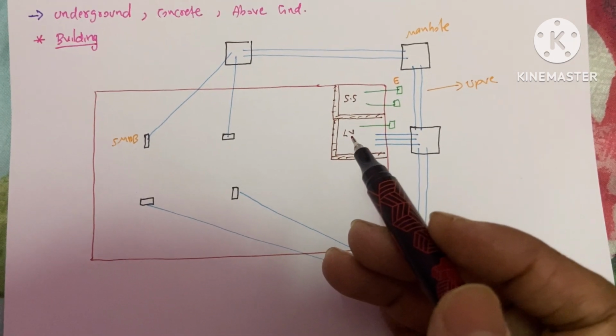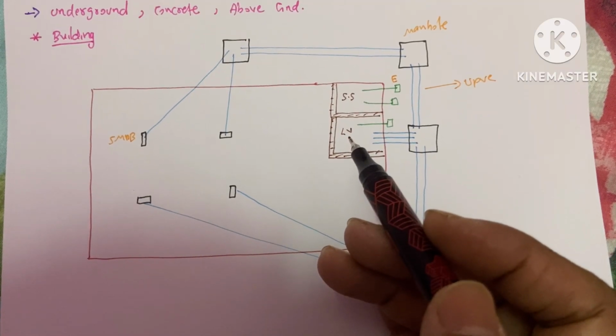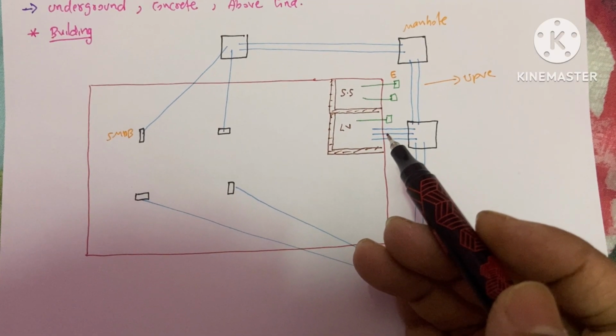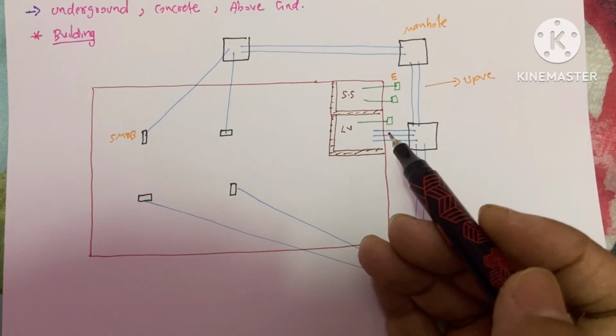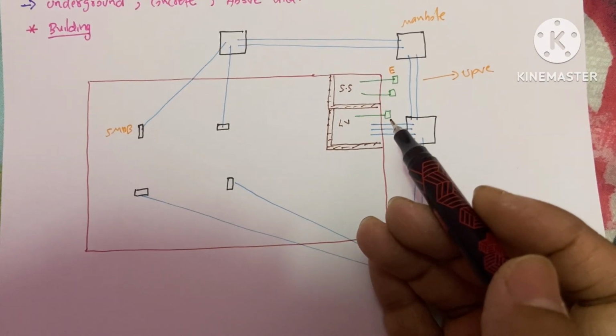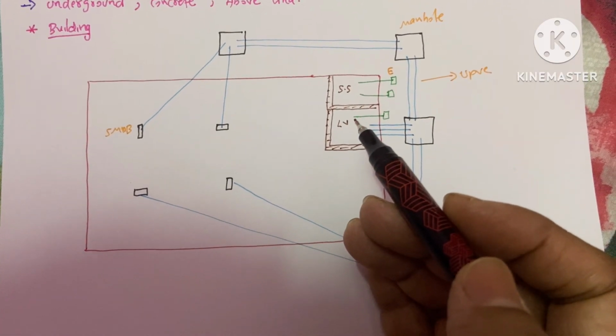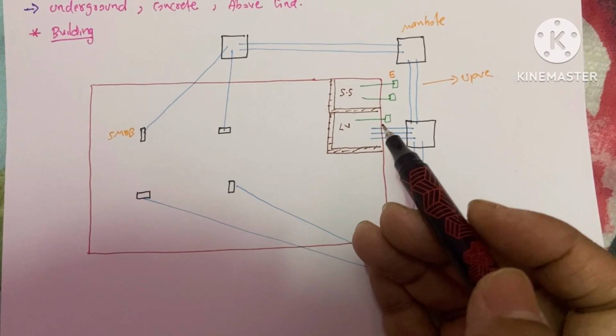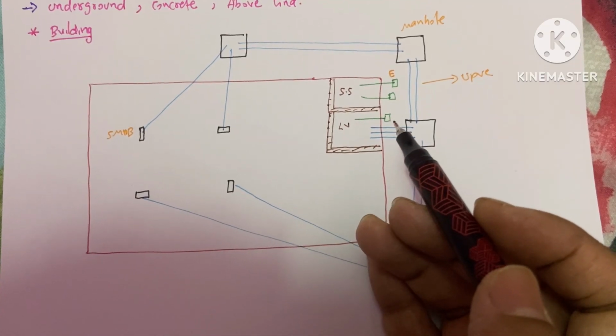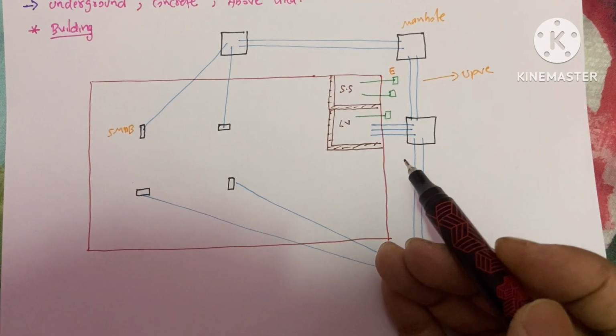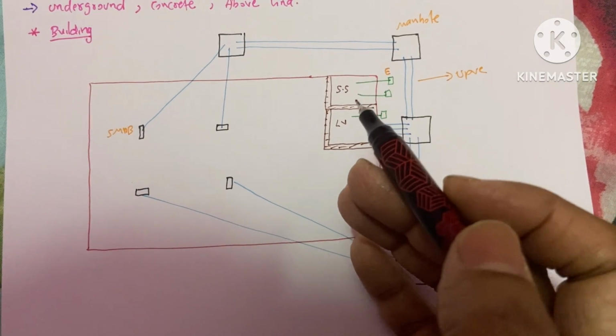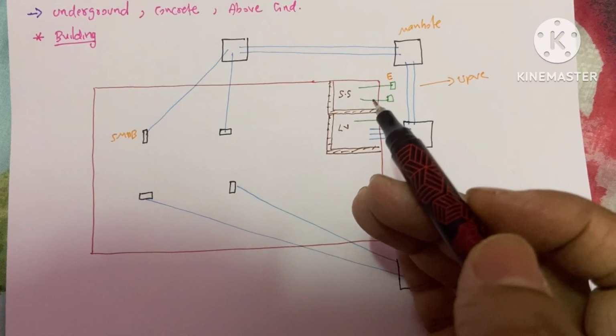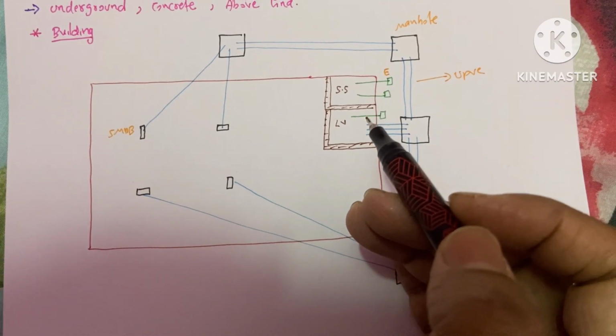Just like that, in the LV room there would be different panels, MDBs, which also require earthing. So from the LV room we would lay UPVC duct underground to the earth pit outside of the building. We require the laying of pipe underground, and the better option is UPVC duct.